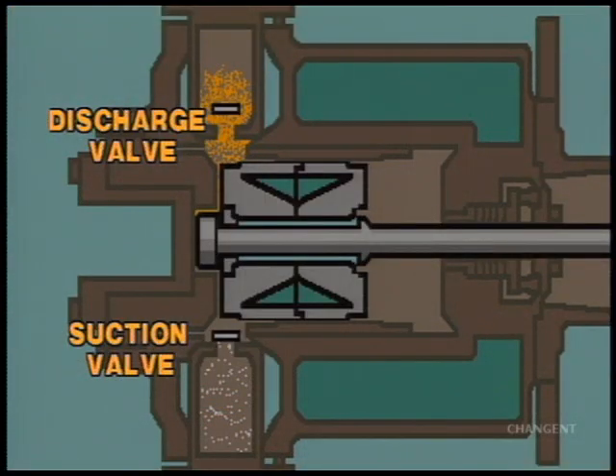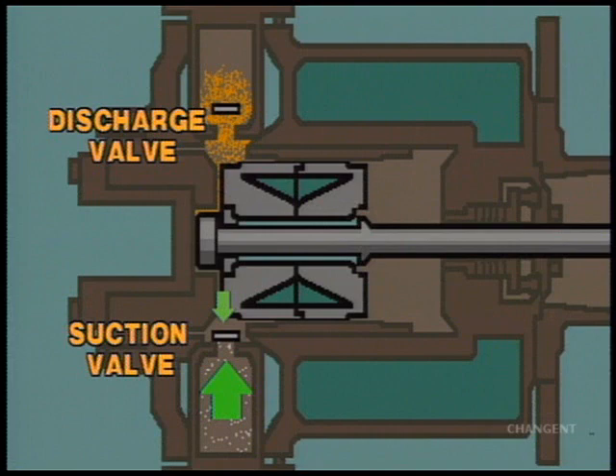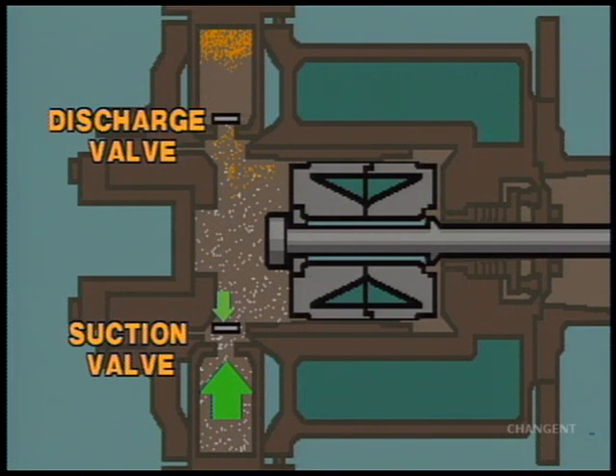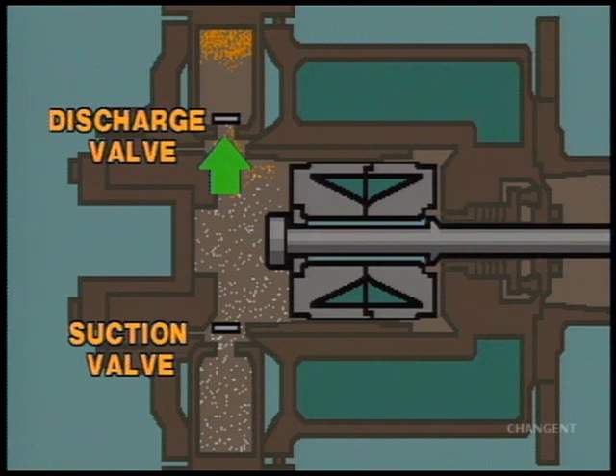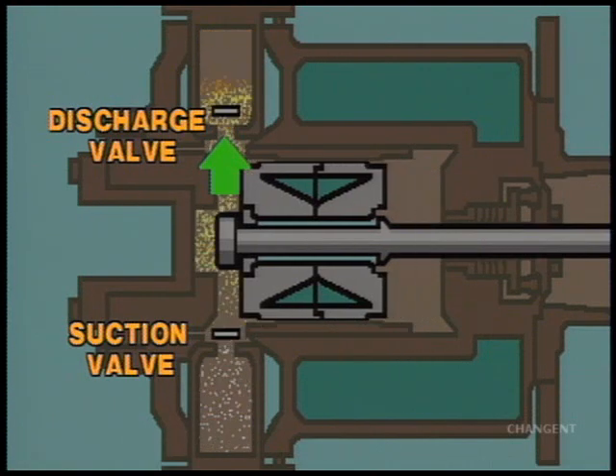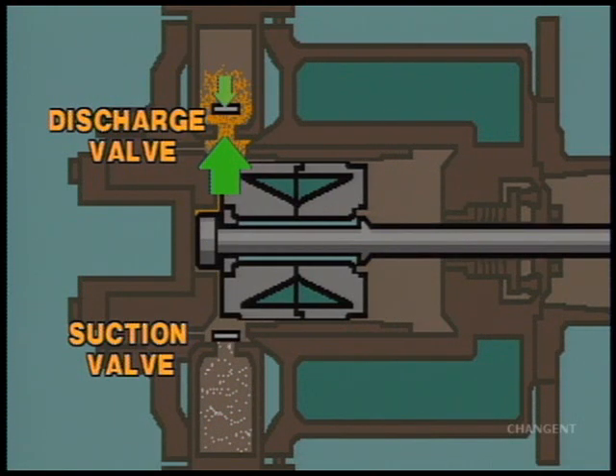So in the case of a suction valve, a lower pressure inside the cylinder and a higher pressure outside the cylinder cause the valve to open, allowing gas into the cylinder. The reverse is true for a discharge valve — the compressed, higher pressure gas escapes the cylinder to a lower pressure area through the discharge valve.